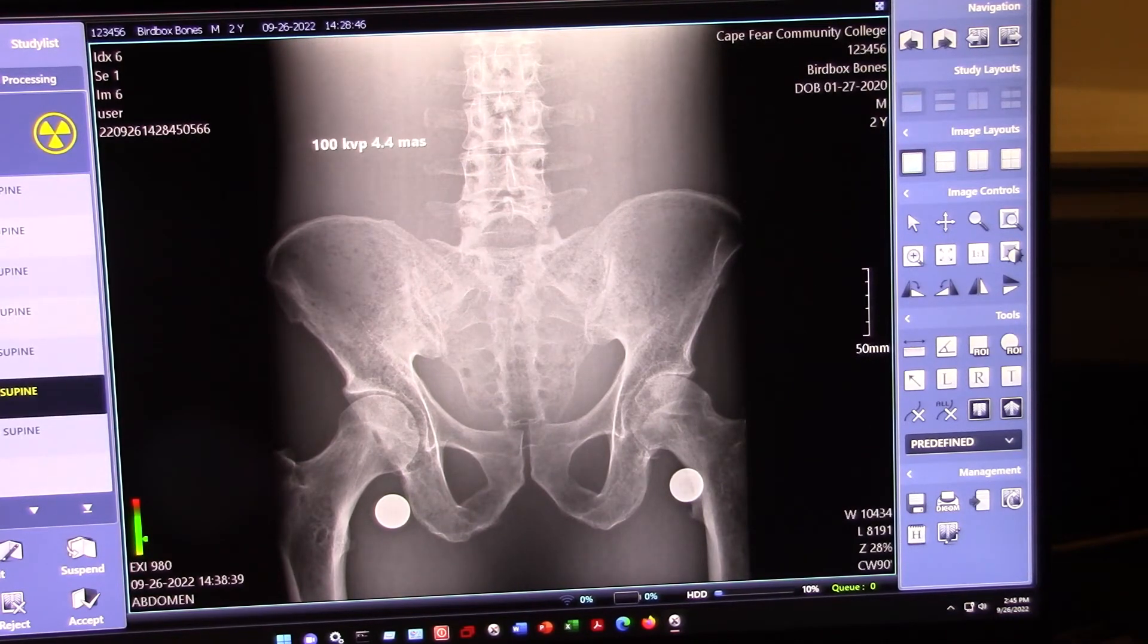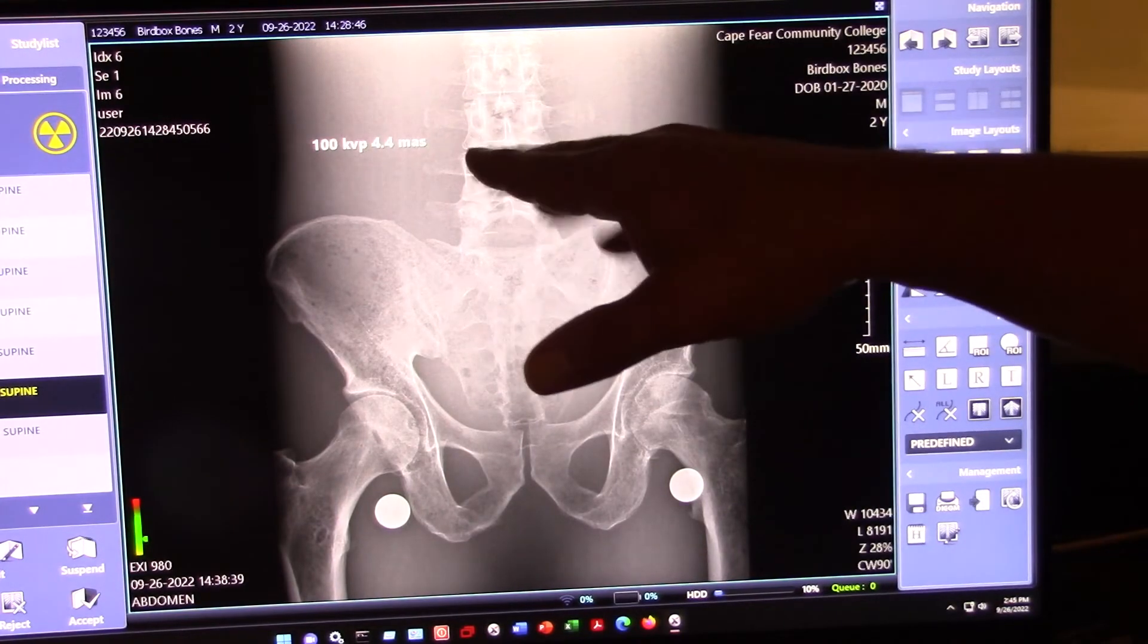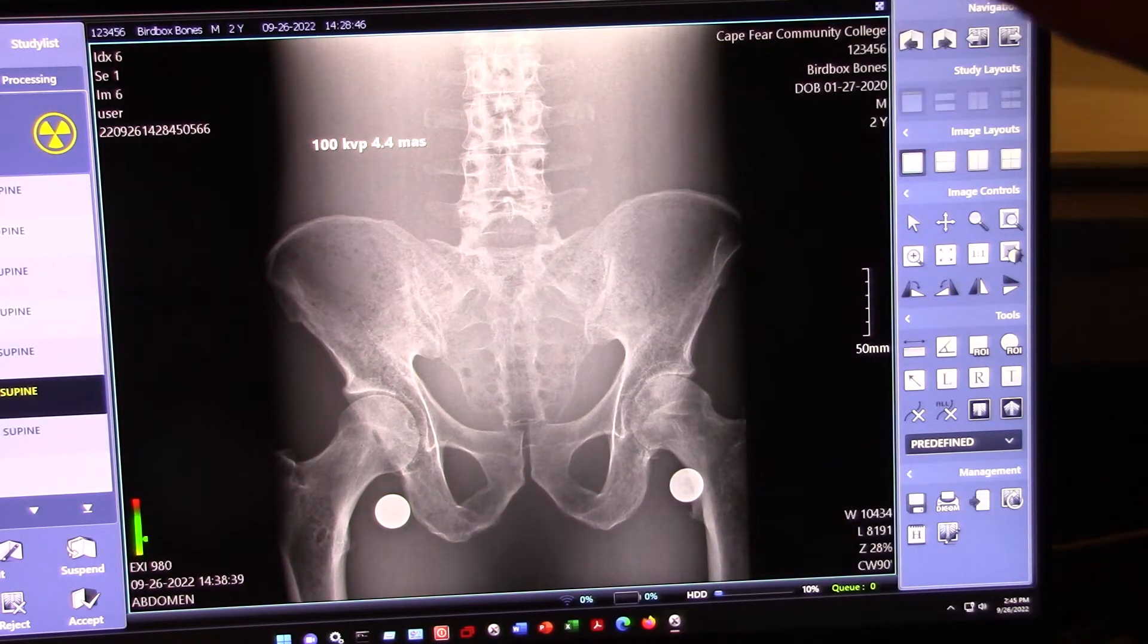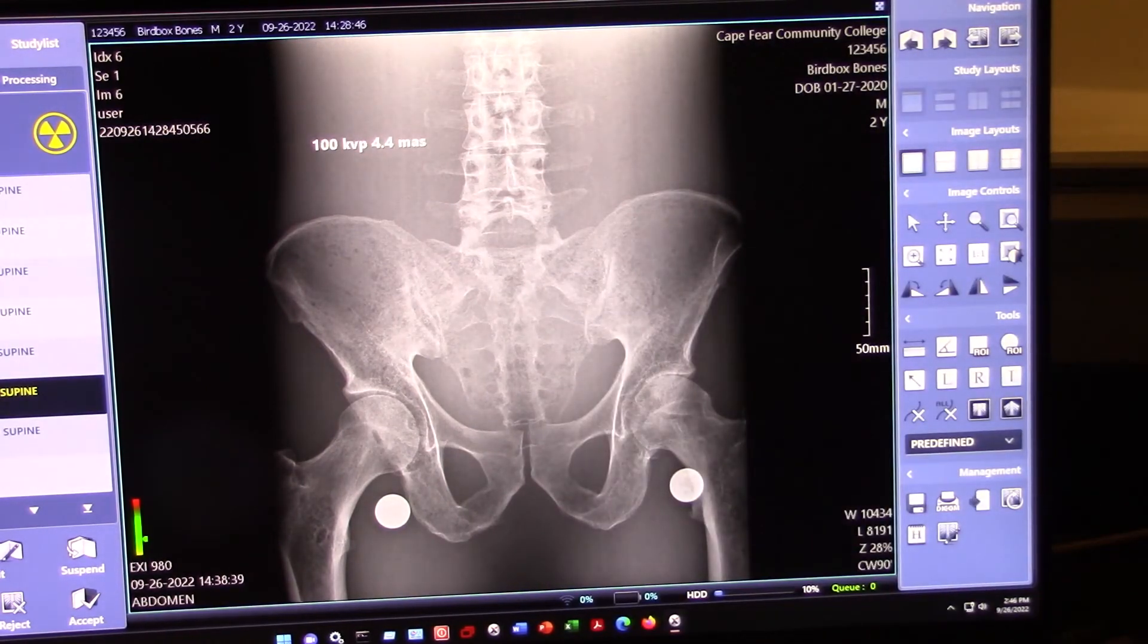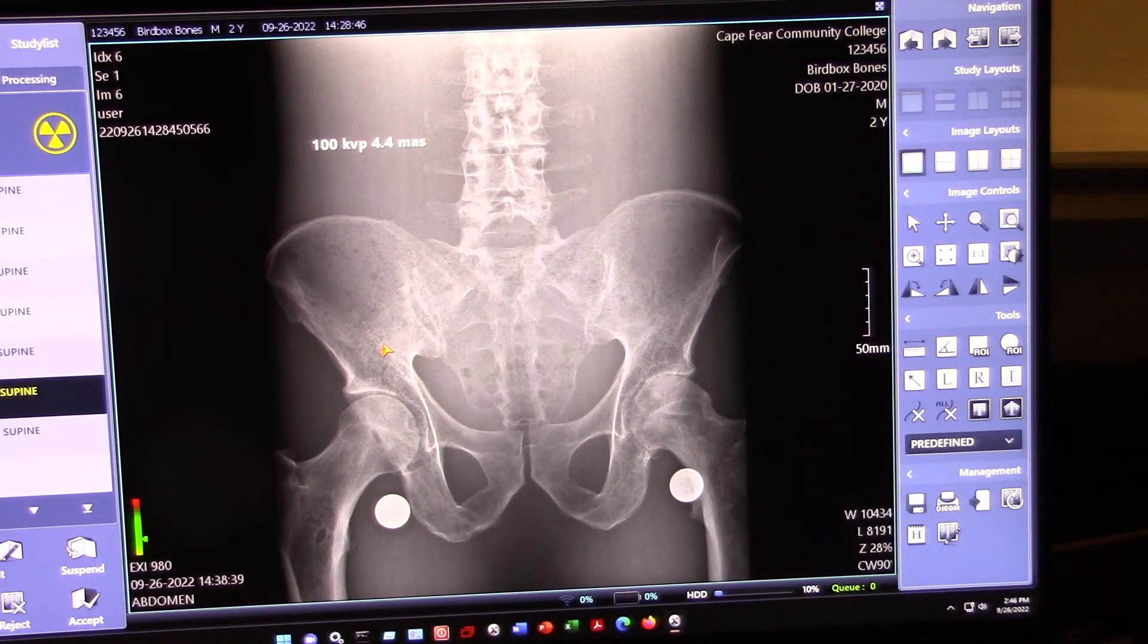Then we go to 100. Not that big of a difference, but you can definitely see we've lost some contrast. So, everything is starting to look more washed out. We don't have the strong delineation between one tissue border and another. We can still get away with it, though. Can we do abdominal radiography at 100 KVP? Yeah, sure, we can. Especially if it's a good-sized patient.